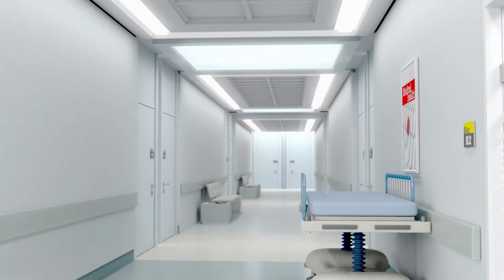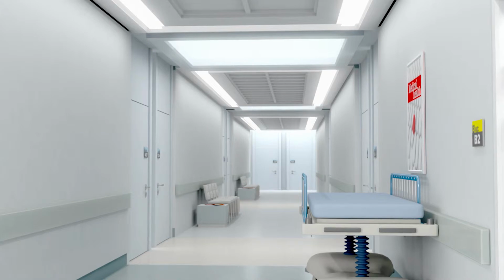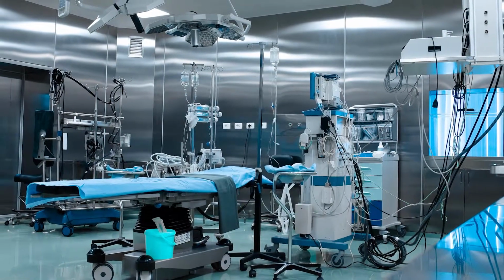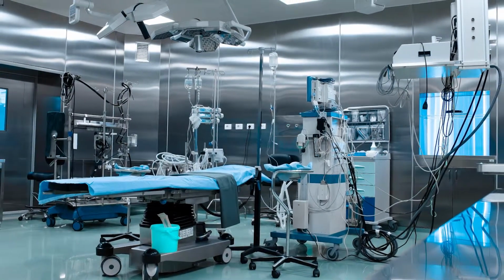Recommissioning follows basically the same steps as commissioning. You're going to verify sequences of operation, verify the equipment is turning on and off, that valves are modulating, dampers are opening and closing, and that temperature sensors and other vital field devices are calibrated and reading accurately. This is very critical, especially in a healthcare facility, where you have critical set points for operating rooms and emergency rooms where temperature and humidity are critical.